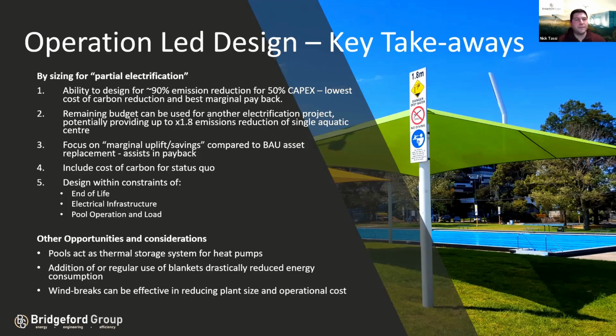Other opportunities and considerations - as mentioned, the pools act as thermal storage systems for the heat pumps. So you have the ability to float the set point, particularly if there's a high requirement for peak load, but that might only occur in 1% of the year. If you're okay with the temperature in the pool floating lower during those periods, you can size the heat pump smaller again. The addition of more regular use of blankets will drastically reduce that energy consumption. If you can cover it when you're not using it, it's fantastic.